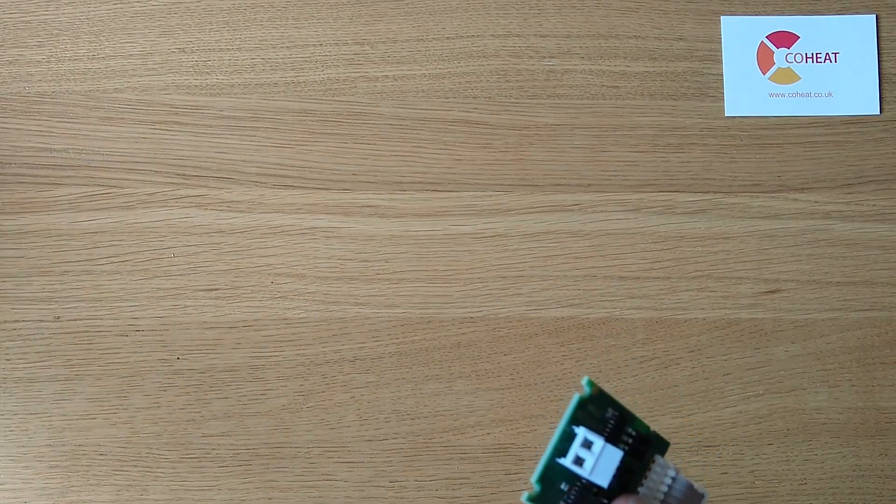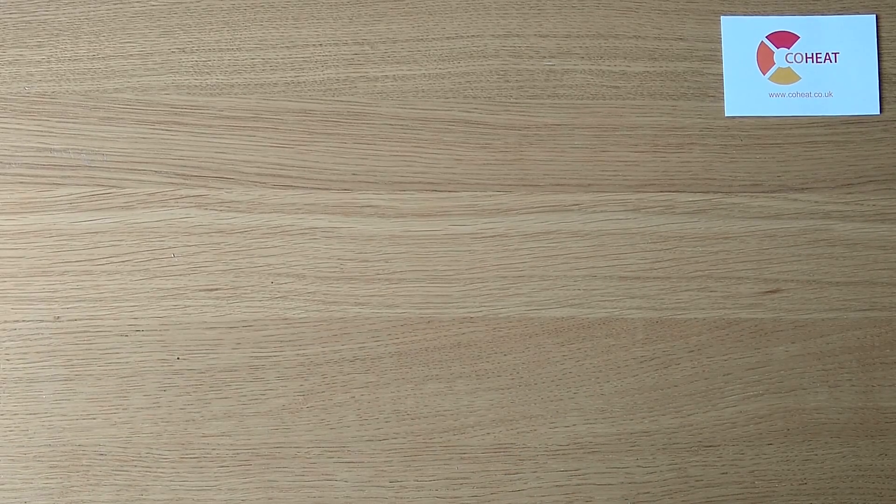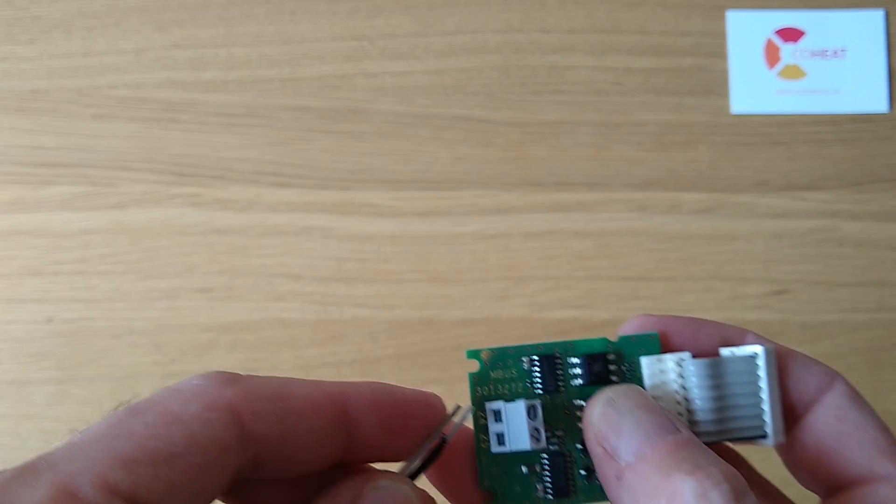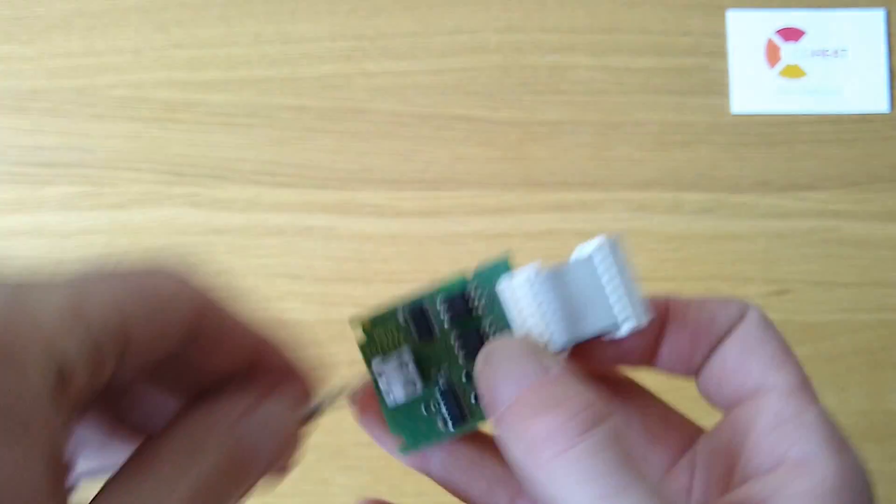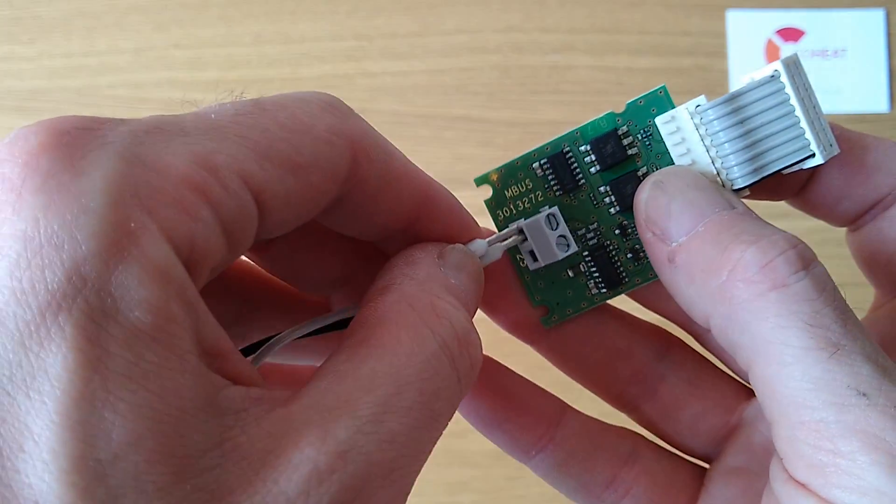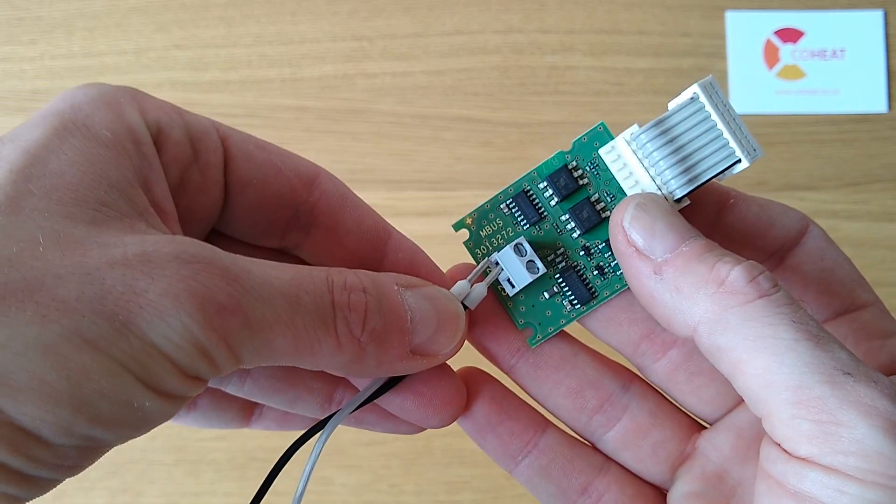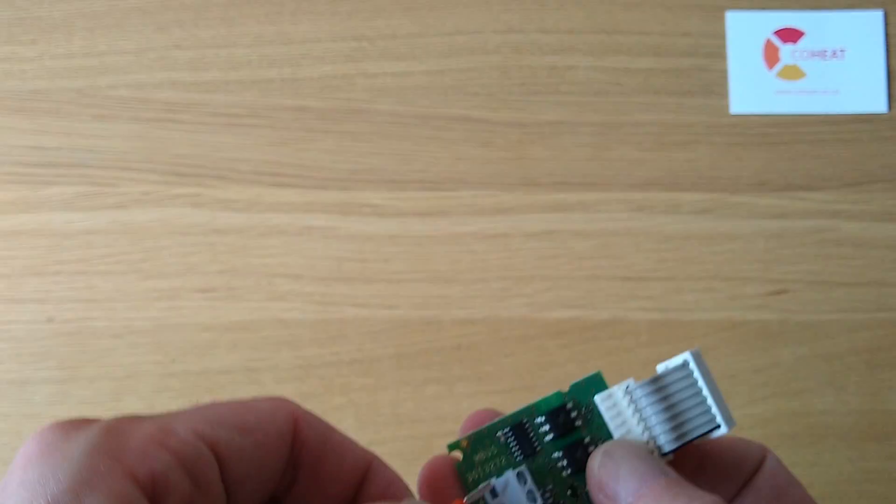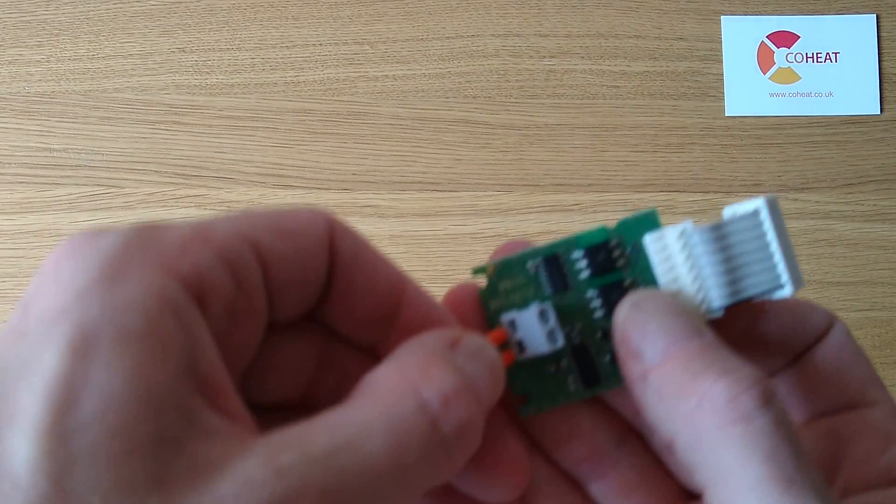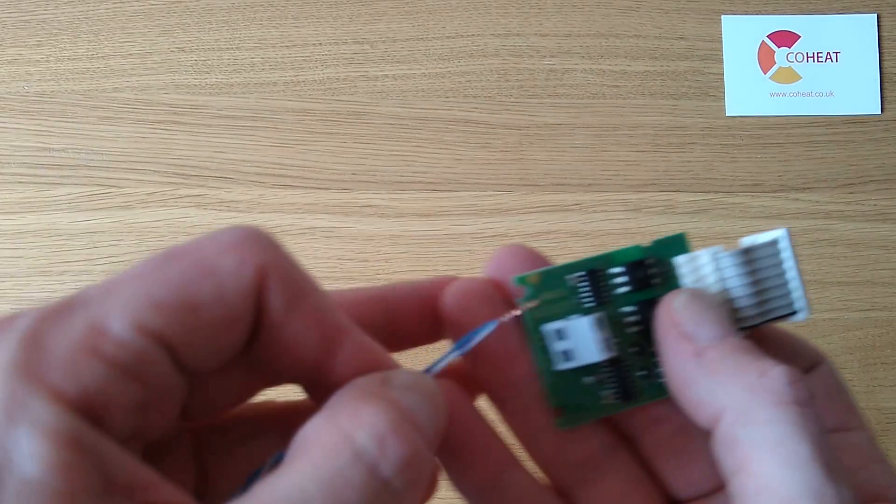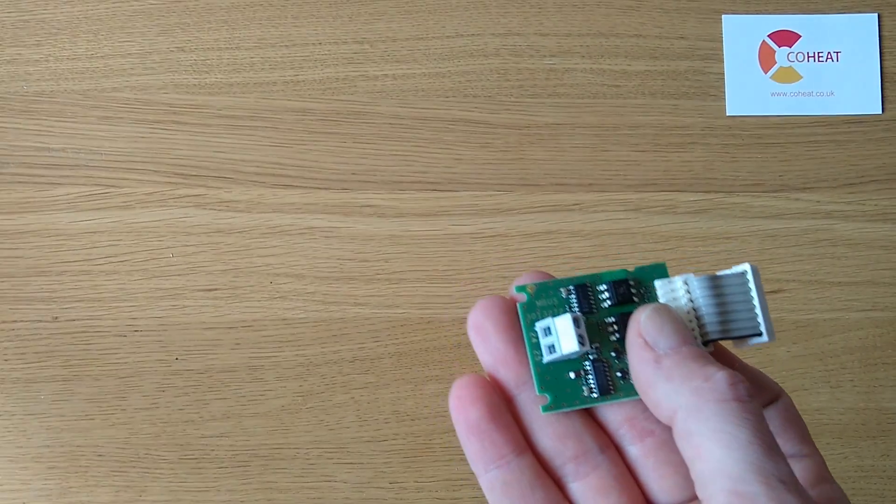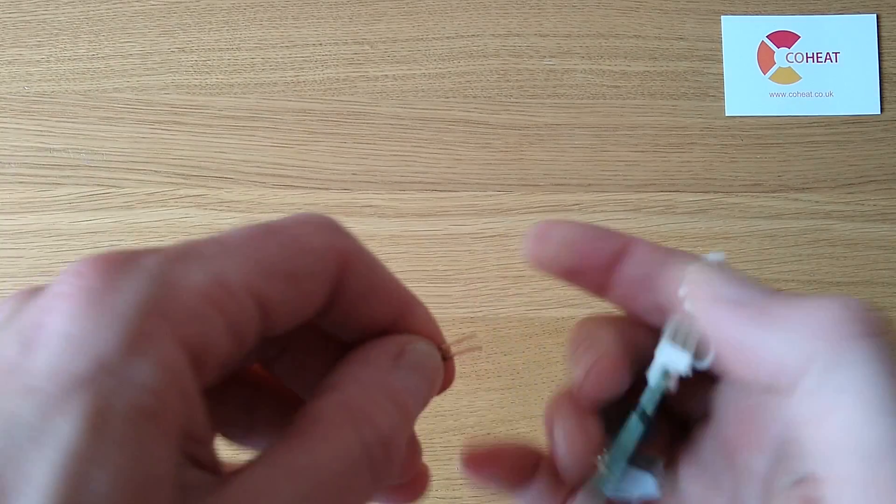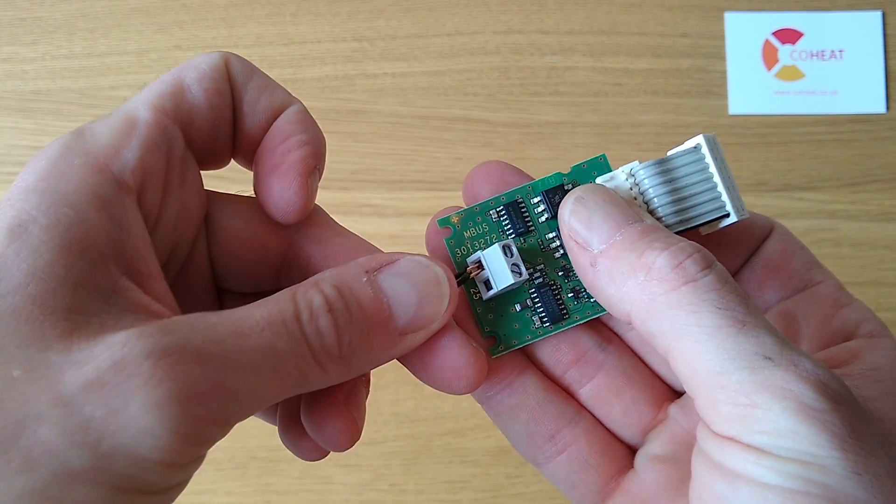We can take our typical Belden 8760. It fits quite easily, and the cage will trap all of that. Can't really use ferrules, there's not enough space in a data card to use a ferruled 8760 type cable. If we're careful, we can use Cat5 twisted, and we can use the KNX type cable straight in as a pair. All of these work well.